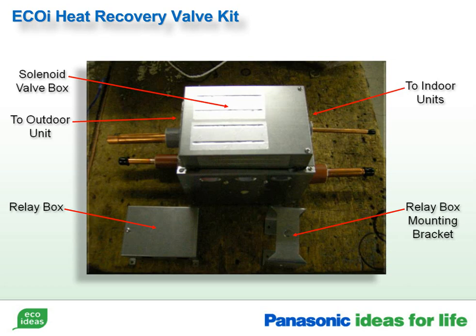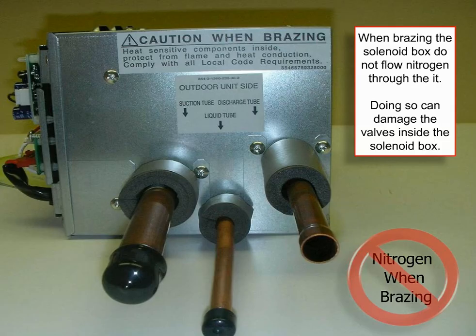These are the main components that are included with the solenoid valve kit. You will find the solenoid box, the relay box, and the mounting bracket for the relay. There is also a 5-foot gray cable, which is not shown in this picture. When brazing, purge the air from the solenoid box, but turn the nitrogen flow off before brazing the connections. The superheated nitrogen will damage the seals in the valves.